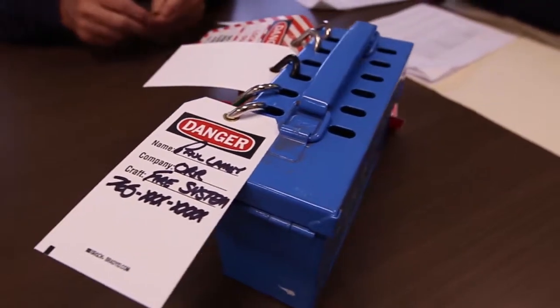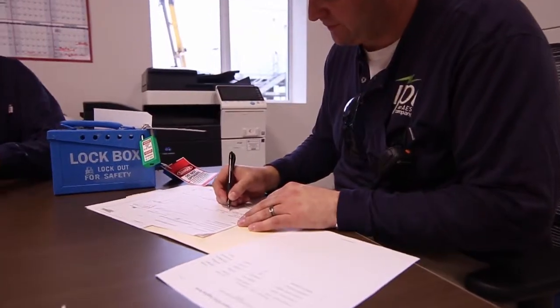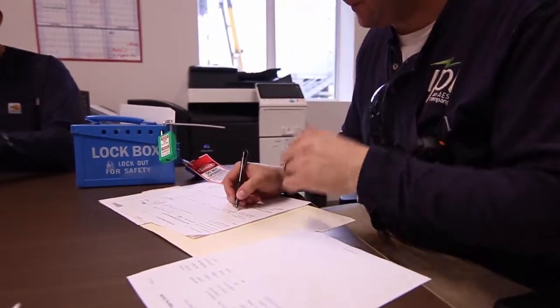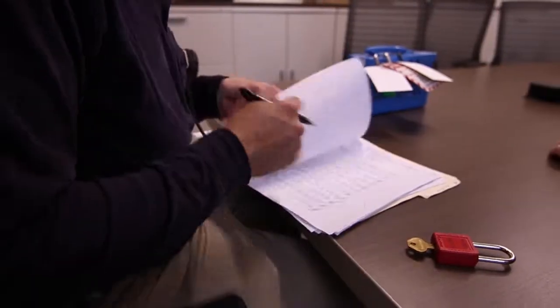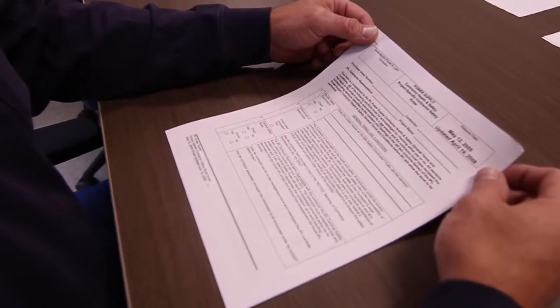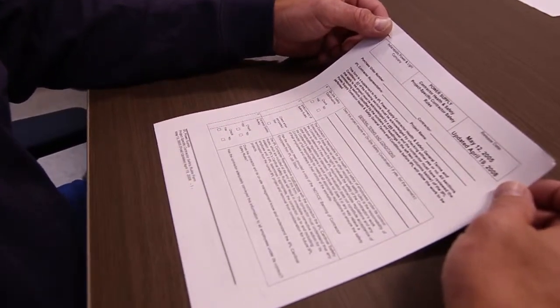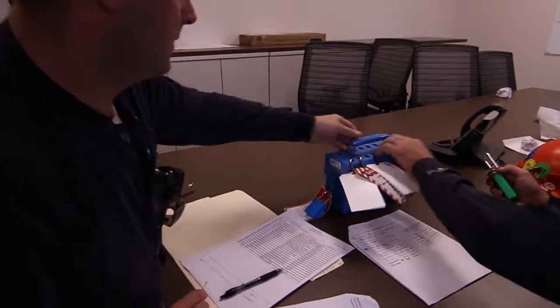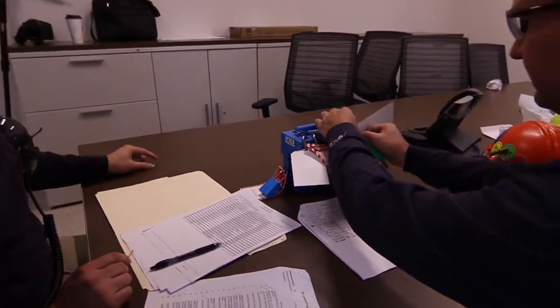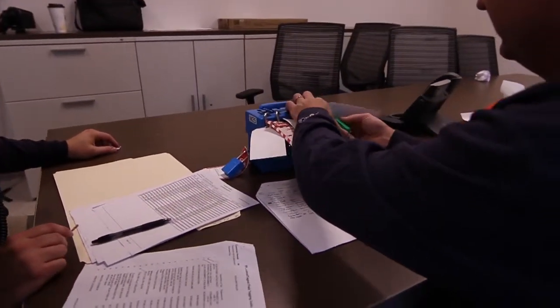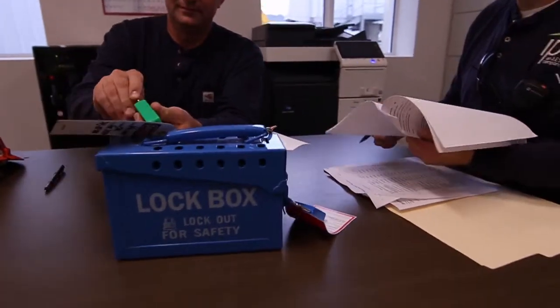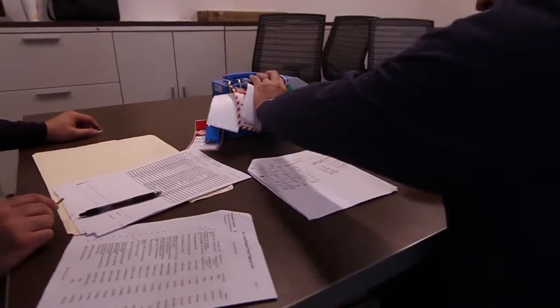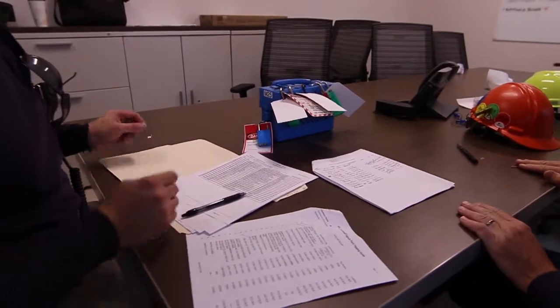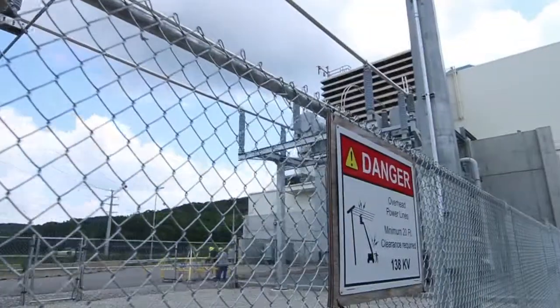You must receive advanced written approval from the IPL contractor administrator to use personal lockout-tagout procedures, and this approval must be documented on the contractor's project-specific form. The IPL contractor administrator must first place their lock on the piece of equipment to be de-energized before allowing the contractor to place their lock. Never place a lock or tag on IPL equipment without proper authorization.